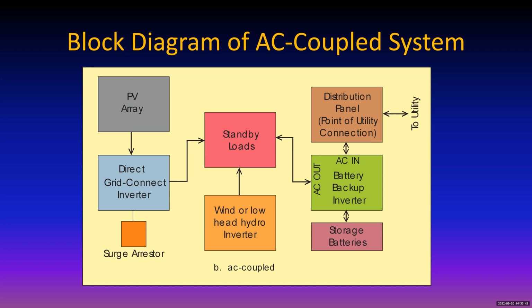Okay, so we see that there are DC coupled and AC coupled systems. This is a basic block diagram of the system. Again, the direct grid connect inverter could very well be a single microinverter for every module in the solar array. You could have 40 modules and 40 inverters right up on the roof, under the modules, so you're actually sending AC down from the roof to your standby loads. If the standby loads don't need it all, it gets sent straight back to the utility.